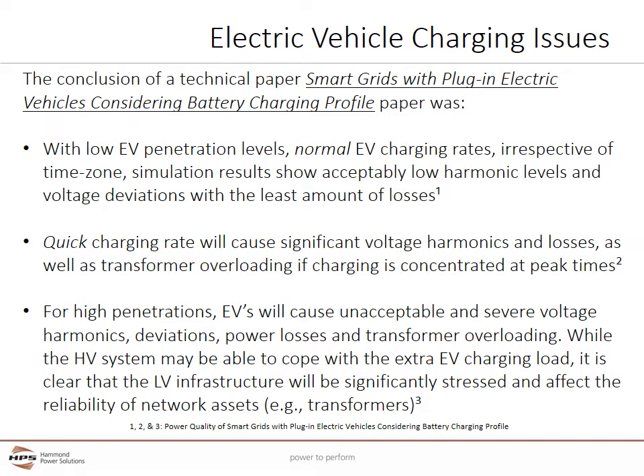Let's now talk about the conclusion of the technical paper, Smart Grids with Plug-in Electric Vehicles Considering Battery Charging Profile, from the chart we just looked at. With low EV penetration levels, normal EV charging rates, which means level 1 and 2 chargers, irrespective of time zone, their simulation results actually show acceptably low harmonic levels and voltage deviations with the least amount of losses. Keep in mind, this is with low EV penetration, which is where much of North America is currently at. If we add quick charging rates from level 3 chargers, they will cause significant voltage harmonics and losses, as well as transformer overloading if the charging is concentrated at peak times.